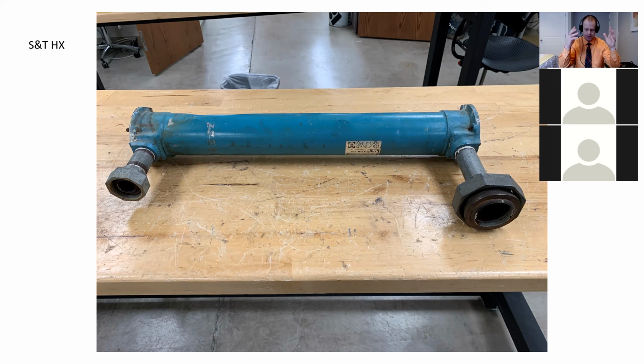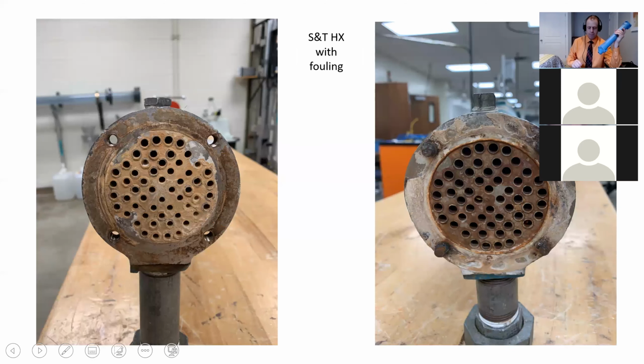This was like 40 years old. If you look at the tube bundle sitting like this, you'll see there's a bunch of junk on it - hard water deposits - compared to the other side where there are fewer and you can still see the bare metal. That's what's called fouling, basically just junk that builds up.